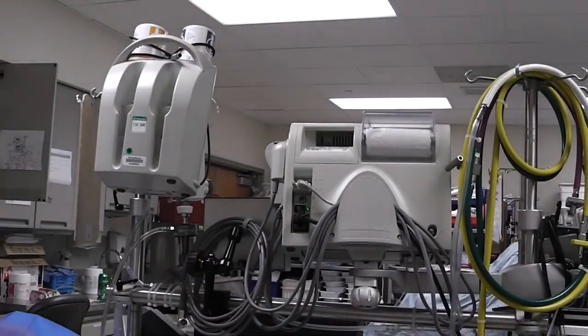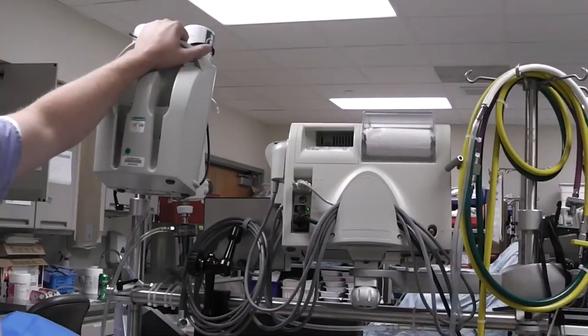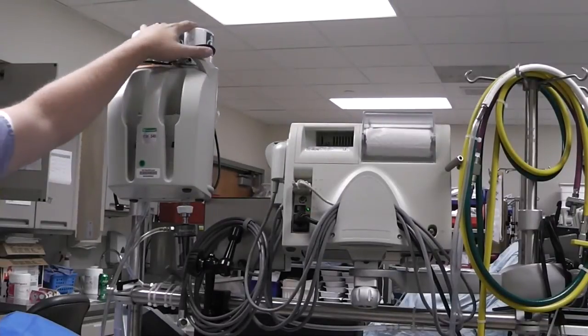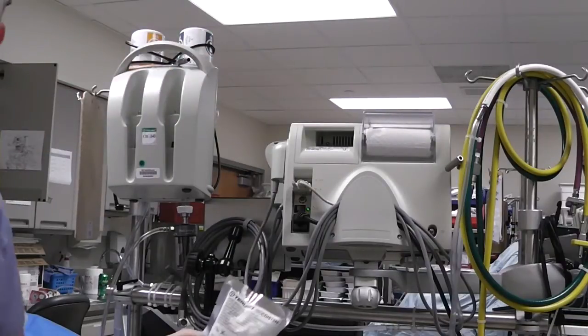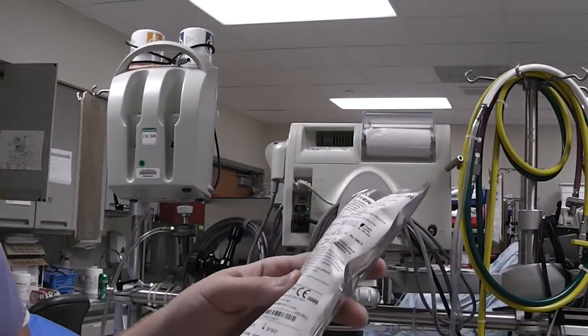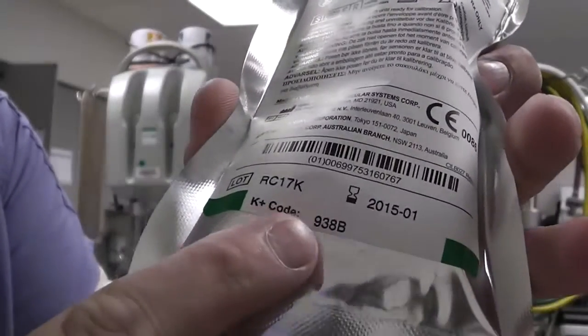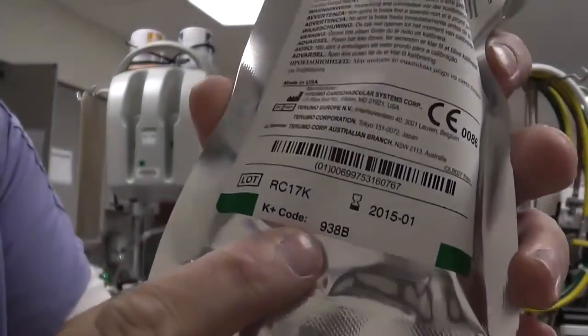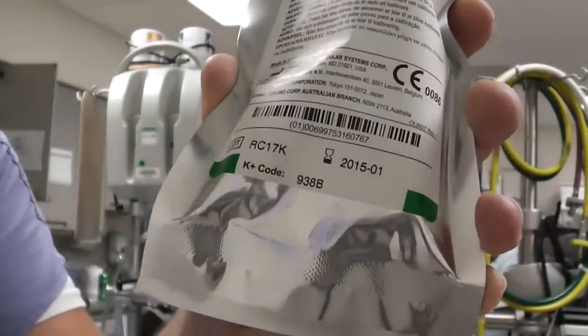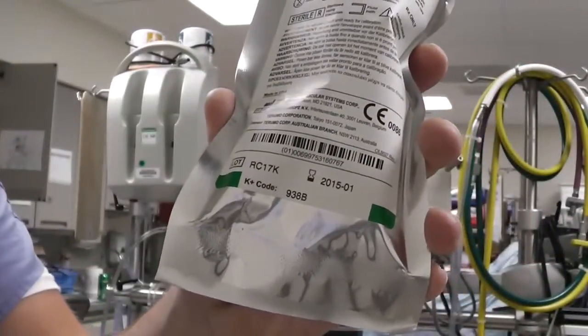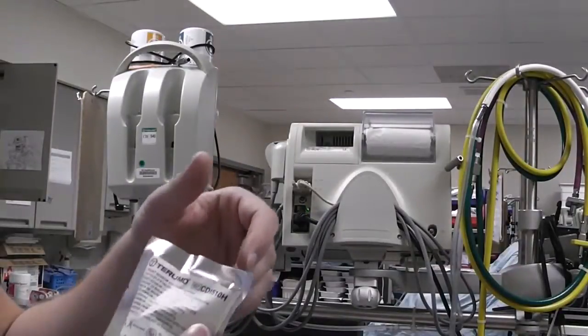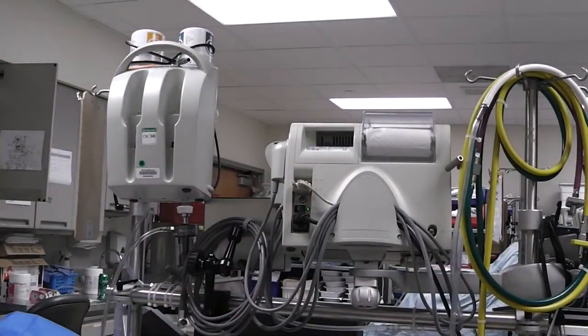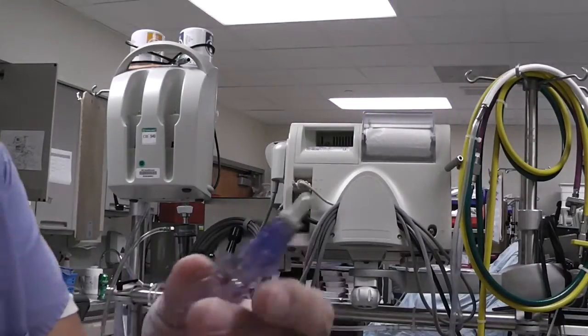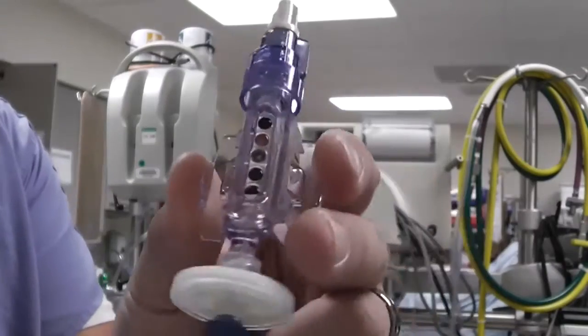Okay, we're at the back side of the pump here. I've grabbed the calibration equipment for the CDI. I like to just hang it on the IV poles here. And I've also grabbed the CDI sensor. So we're going to take note of this number here. This one happens to be 938B, and we're going to remember that number for the CDI. So we're going to open this packaging, remove the sensor, and this is what it looks like.